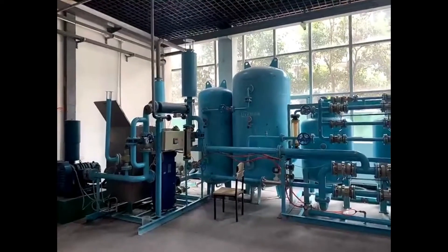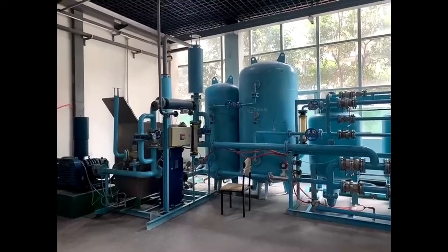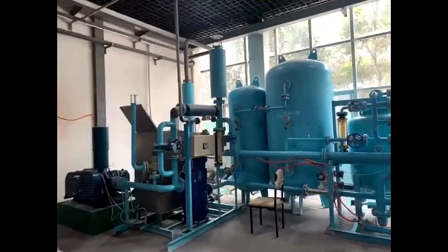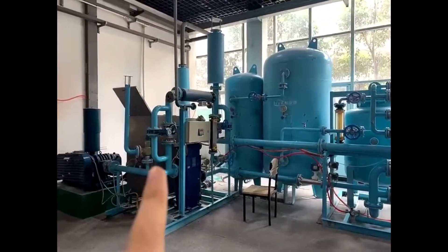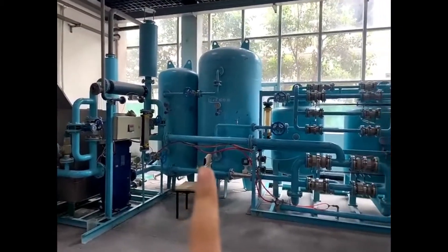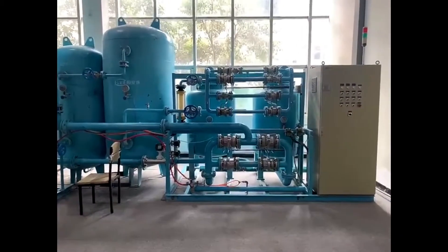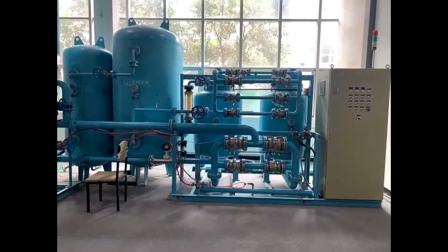Now you can see our VPSA facility. VPSA means Vacuum Pressure Swing Adsorption. This facility is mainly for air separation and purification. This one has a blower, and in the middle this unit is a cooling unit, mainly for balancing the pressure. These two small towers — one is for adsorption, the other one is for regeneration. Normally we put our molecular sieves into the two towers and we do the test.